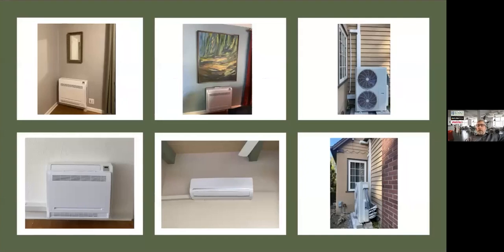Another situation is that many single-family buildings and multifamily buildings use some form of a ductless mini split or even a ducted system. This is a retrofit that I did on a single family home. And we've got a large 4-ton machine outside. We've got a number of refrigerant lines all fanning out to feed various boxes within the home that can provide heating or cooling. Between the outdoor unit and all of those individual heads is a line charged with refrigerant.